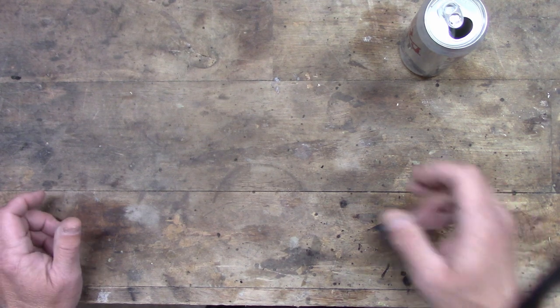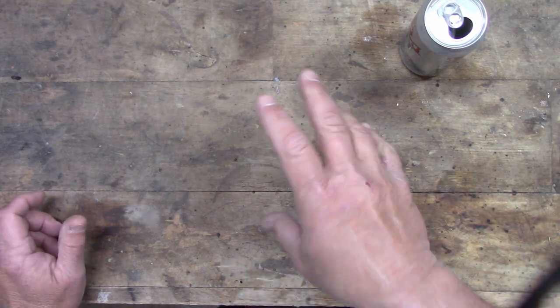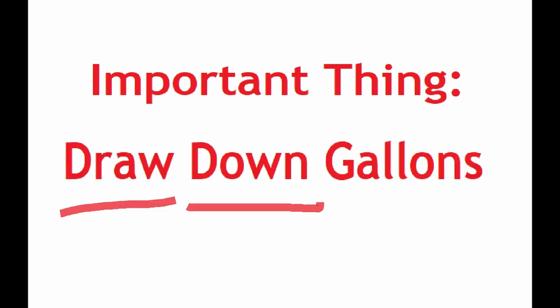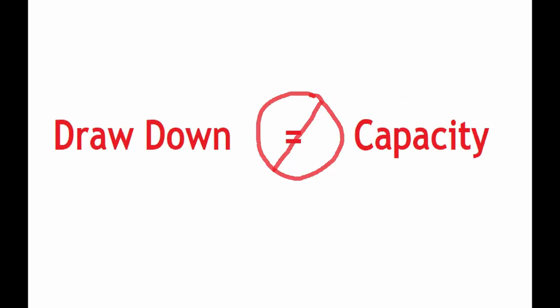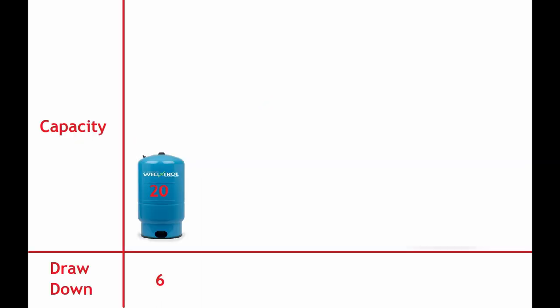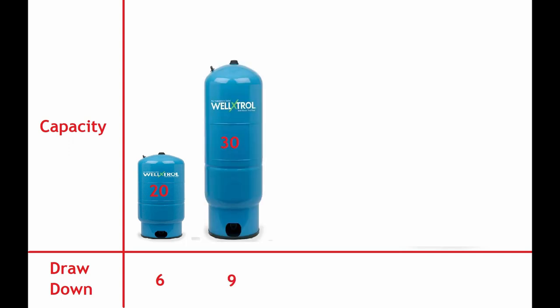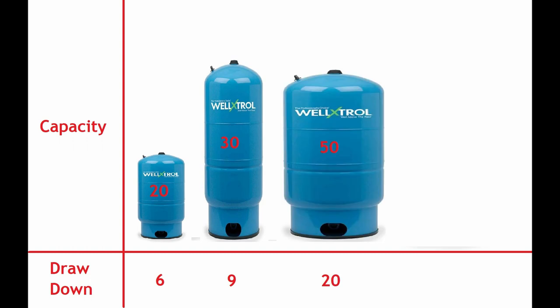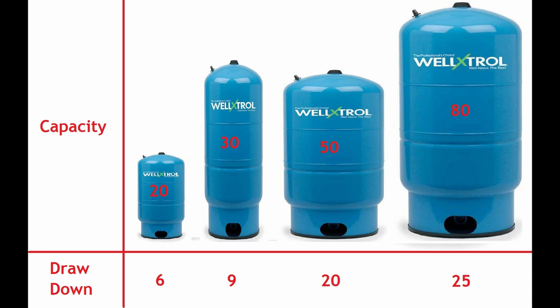Picking a tank can be a bit confusing, but there's an important thing you need to know: the drawdown gallons. Drawdown gallons is different than the tank's capacity. For example, a 20 gallon tank might have a six gallon drawdown, a 30 gallon tank might have a nine gallon drawdown, a 50 gallon tank might have a 20 gallon drawdown, and an 80 gallon tank might have a 25 gallon drawdown.